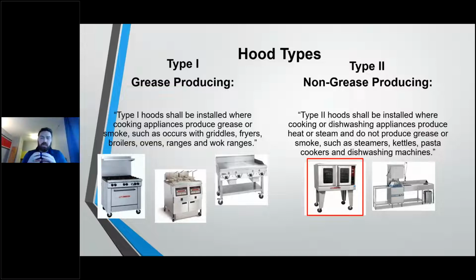And in my personal experience, most code officials are going to go to the worst case scenario. So, hey, is there a probability or a possibility that at some time in the future, this convection oven or this combi oven that is currently being used for heat only, is there a possibility somebody could throw a pan of grease or a pan of bacon in there and make quite a bit of grease production? If yes, then most folks that I've interacted with are going to go on the more conservative side and require a type 1 system. But that's really the only time you have to think about, is this a type 1 or a type 2 system? It's these in-between items where it's truly just heat up, reheat, that's not going to have any grease production, or is there a possibility for grease production? So not a lot for you all to think about on that side of things, but those are your two options for your hoods.